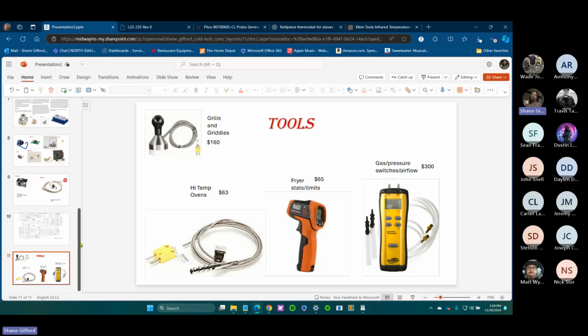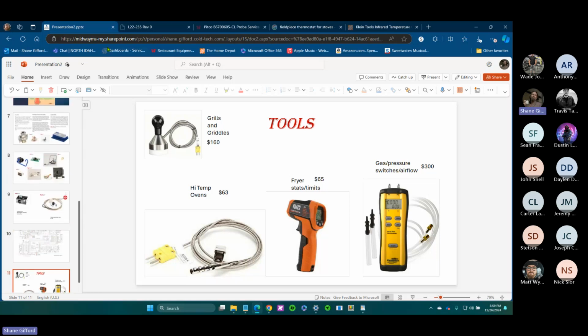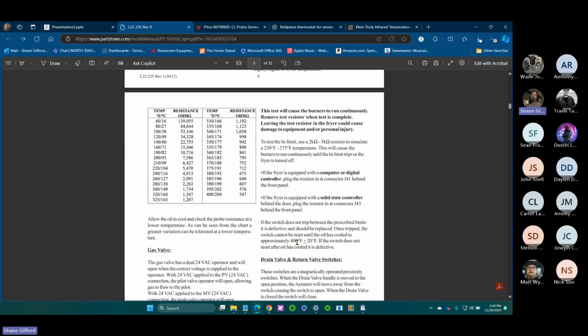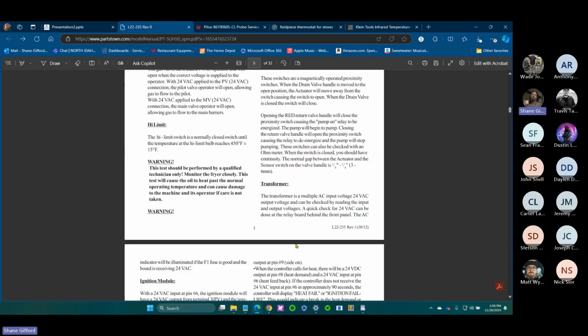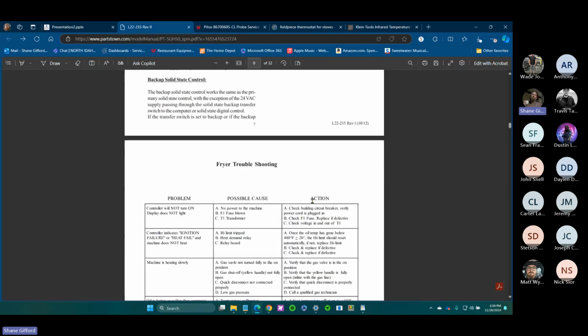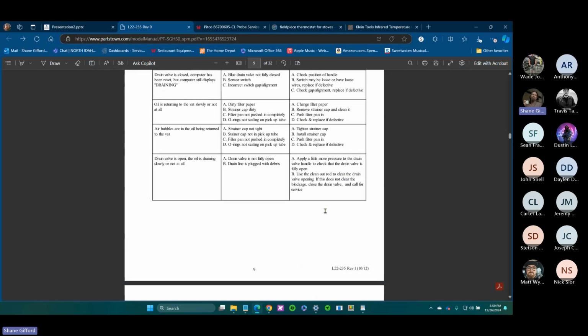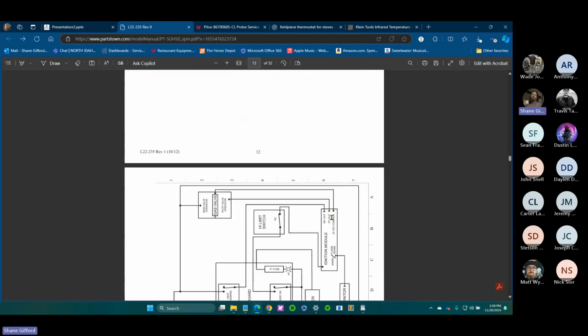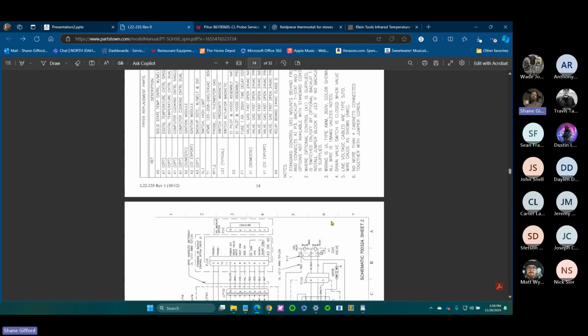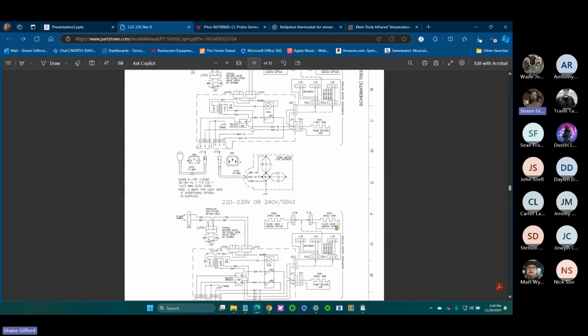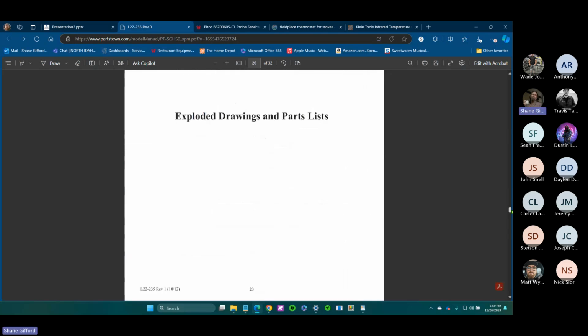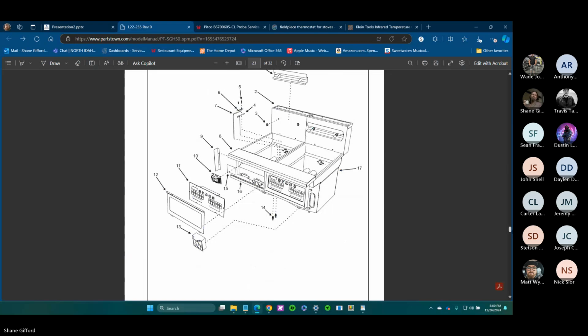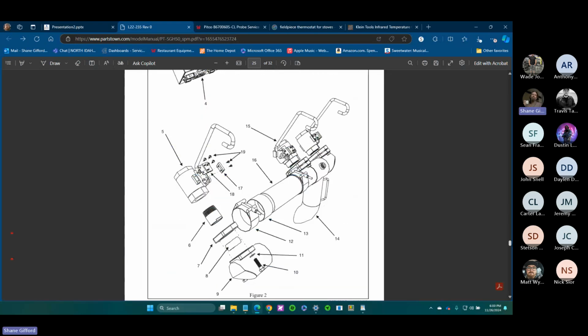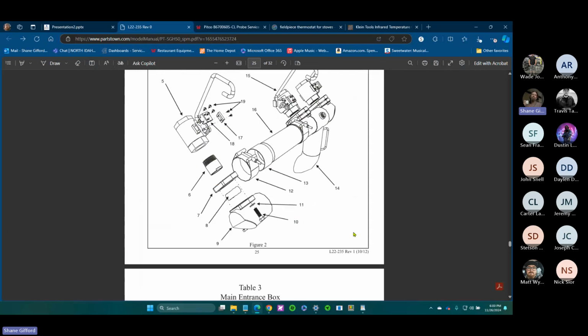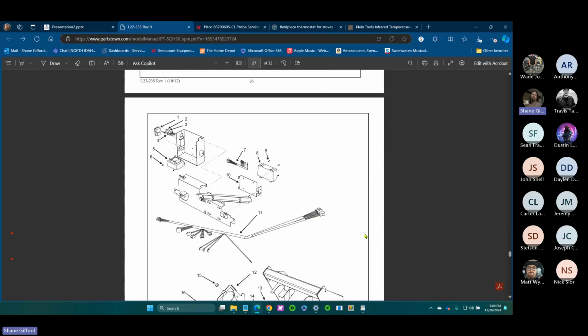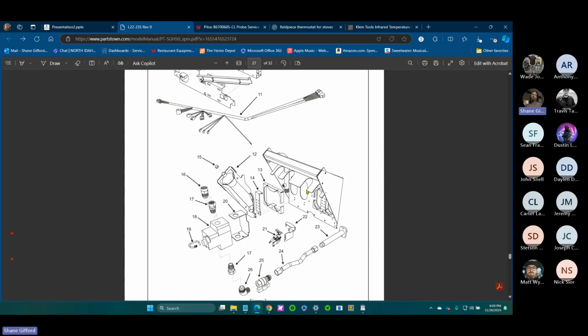Almost every single cooking appliance has a gas valve, but then you're also going to have a regulator, because oftentimes in a restaurant, when your pipe comes in from the meters outside, you're going to have a big fat line, and then each of your fryers and hot side appliances are tapped off of that line. In between the gas line coming in and your manifold, you're going to have a regulator, which all it does is lower your gas pressure to the gas valve. Most gas valves are rated to only receive a certain pressure behind them. Most of them, I think, are like 7-8 inches on a typical gas valve.